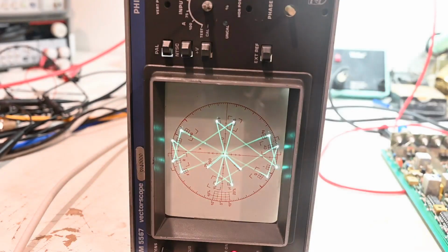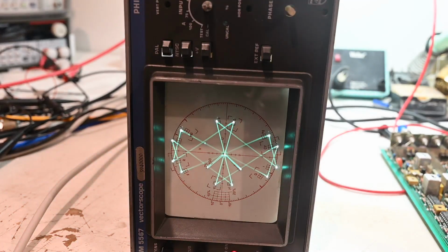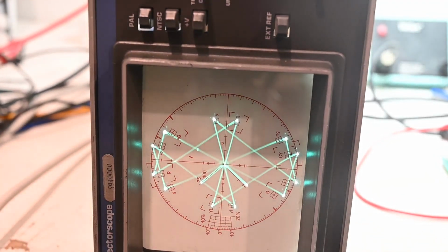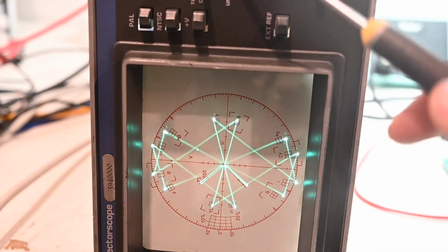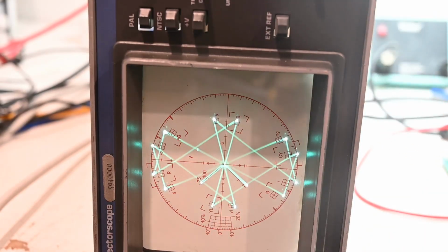Now this, in the past, when I would apply some heat to the PCB, that would make it go completely crazy. It's not responding to that anymore. So now it seems to be pretty reliable. However, we do have some calibration issues here. So if we have a look at the trace, as I say, it is a bit high here, and we're set to 75%. We've got a 75% input, but it's coming up a bit high.